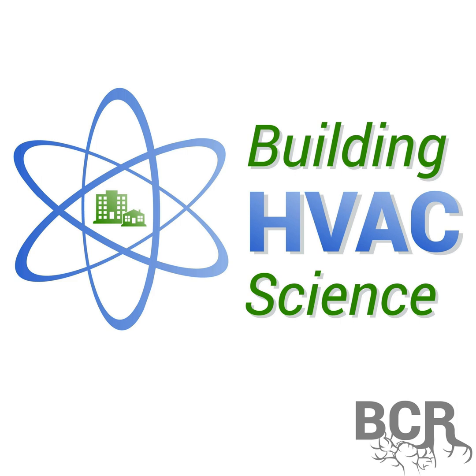And as an appliance-based compressor, the reason we went with that is that appliance compressors are made to be used indoors. So it's a very quiet compressor, similar to a refrigerator compressor. It gives us good efficiency at a small tonnage as well as very quiet operation. And the way this is connected is basically with ductwork from the inside to the outside. There's no element of the heat pump that sits outside. It's all within the conditioned space. Right. It's all a sealed system, a hermetically sealed system, just like a refrigeration system.